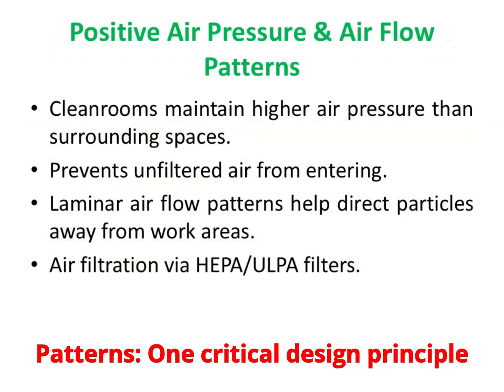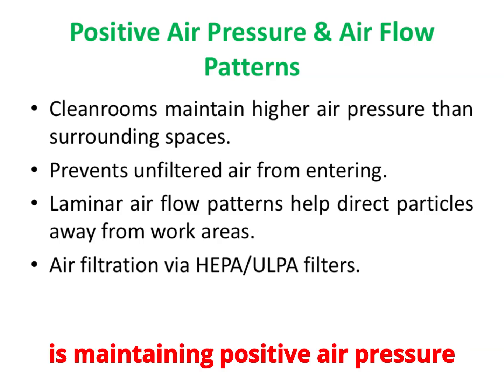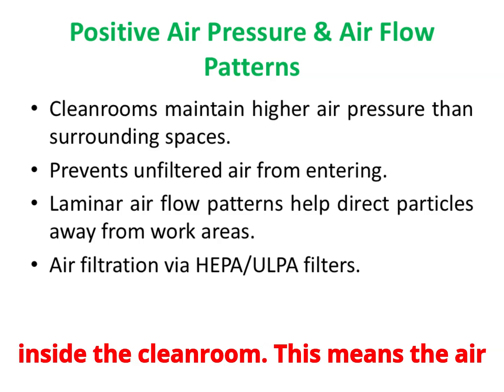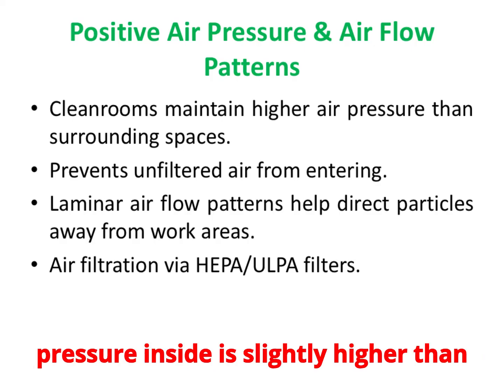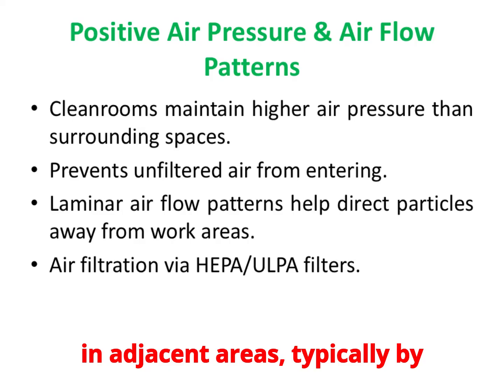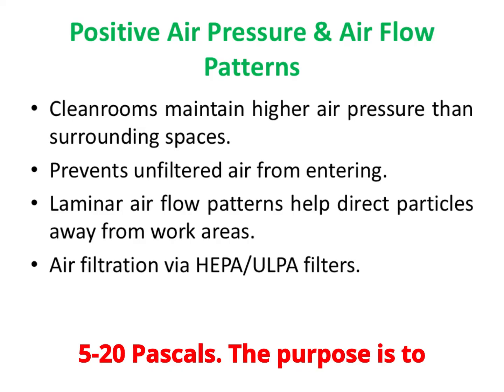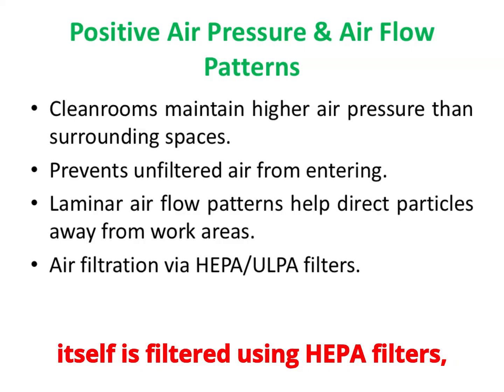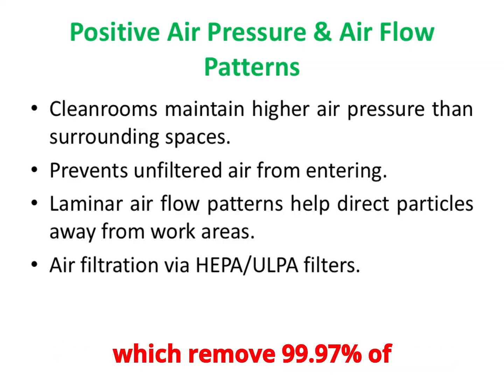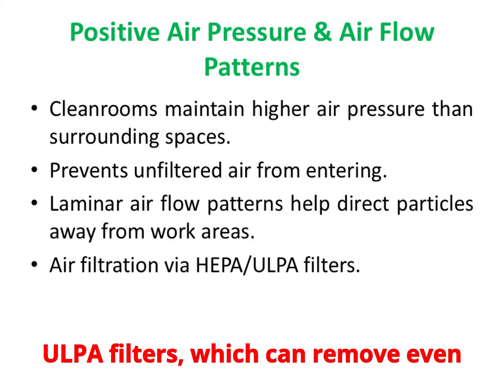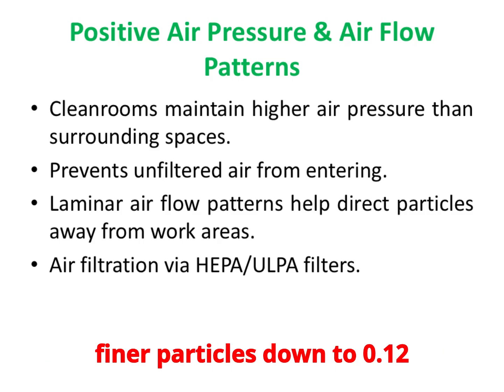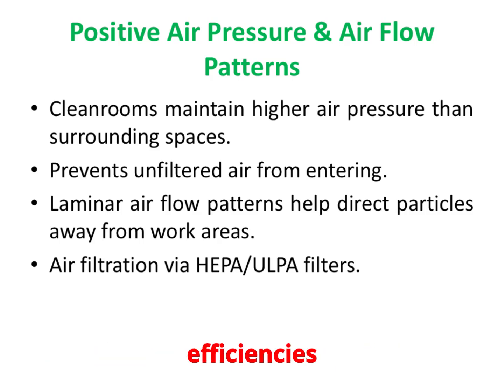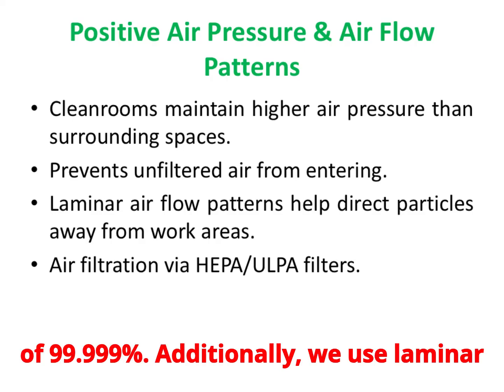One critical design principle is maintaining positive air pressure inside the clean room. The air pressure inside is slightly higher than in adjacent areas, typically by 5 to 20 Pascals, ensuring that whenever a door is opened, clean filtered air flows out rather than contaminated air flowing in. The air itself is filtered using HEPA filters, which remove 99.97% of particles at 0.3 microns, or ULPA filters, which can remove particles down to 0.12 microns at efficiencies of 99.999%.